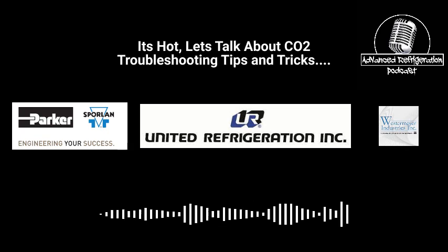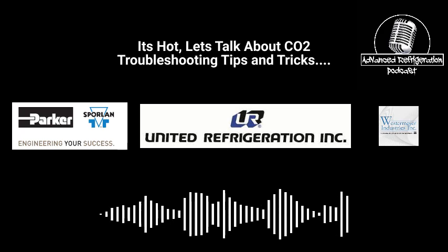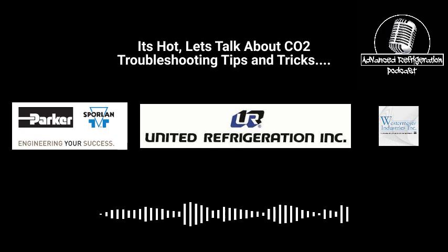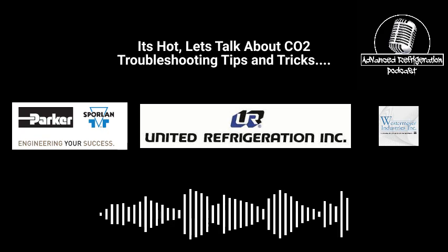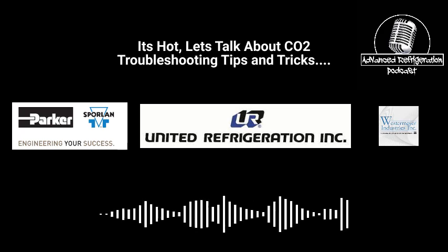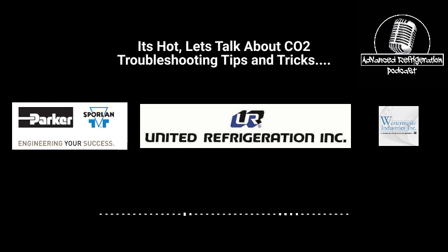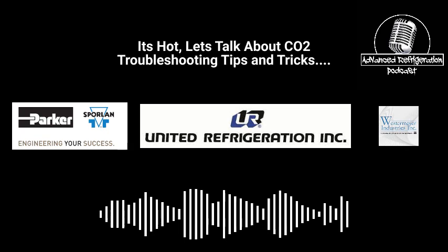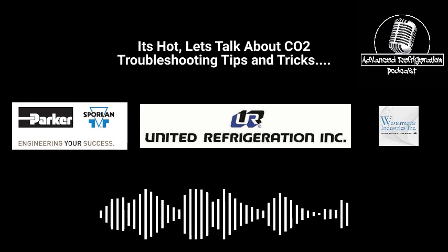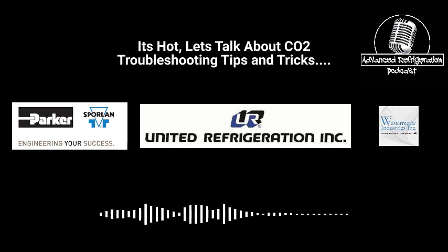Say it's a 20 seconds off period in between. I'll make it like 5 minutes. So however many seconds it is, I'll make it like 5 minutes, so it'll be on for 10 seconds every 5 minutes, or on for 20 seconds every 5 minutes. That way it's still pulsing and draining, but it's not constantly on and it's not constantly injecting gas into the receiver. So those are just hooked up to ROs on the CPC, right?